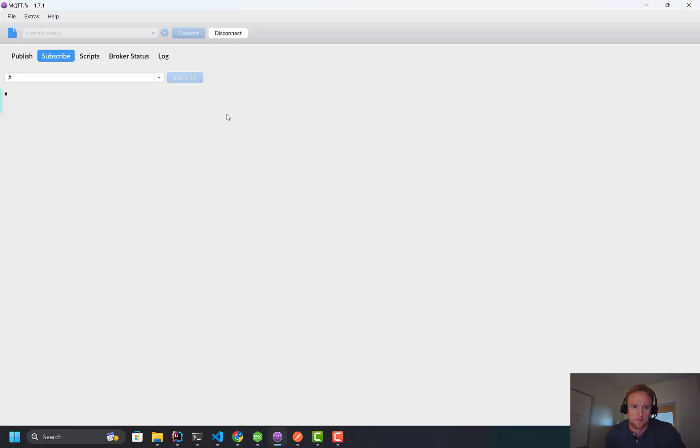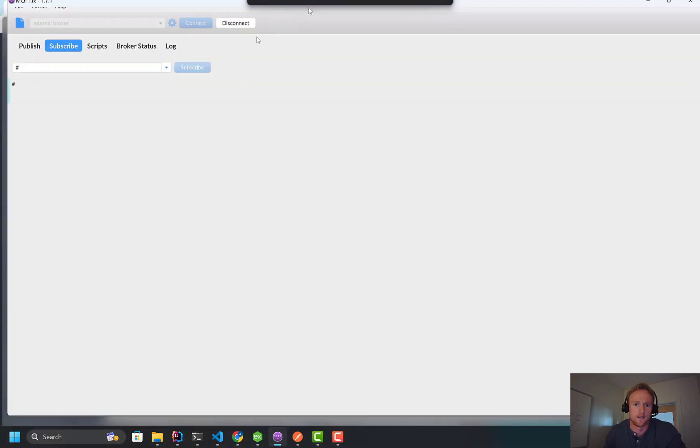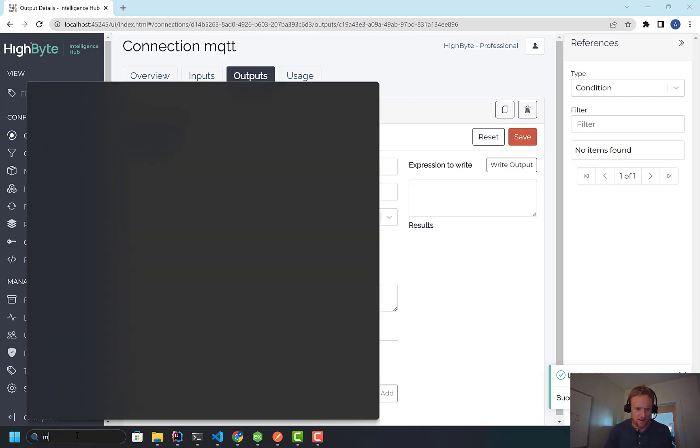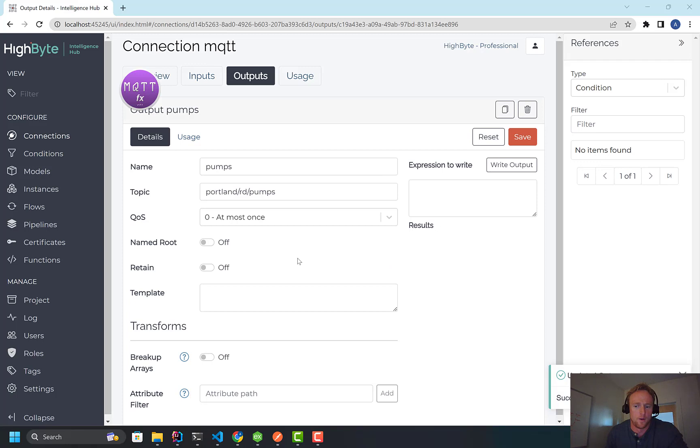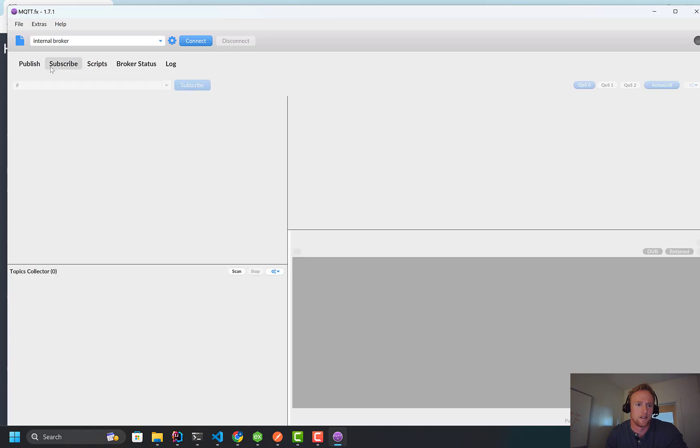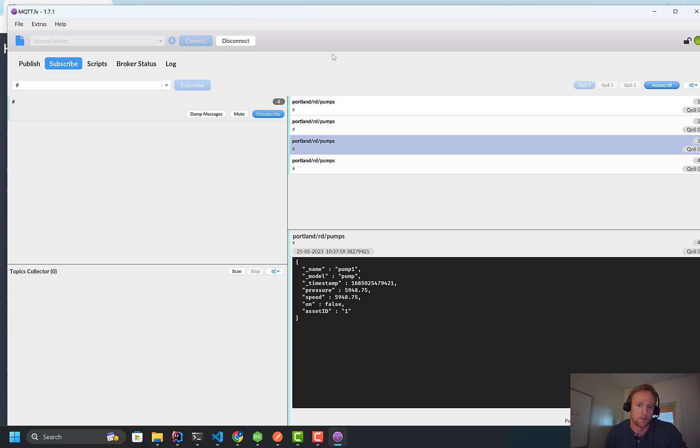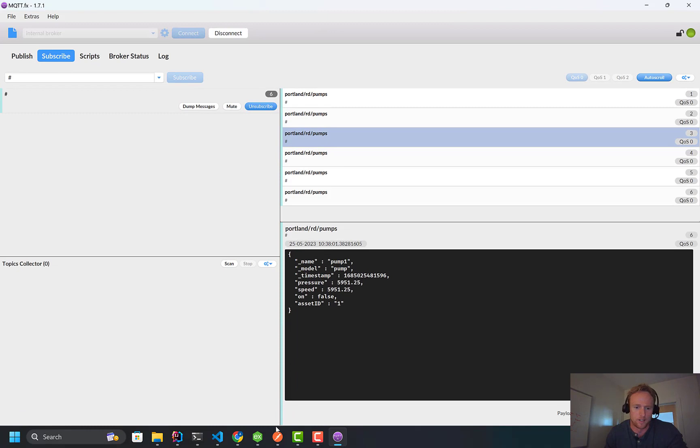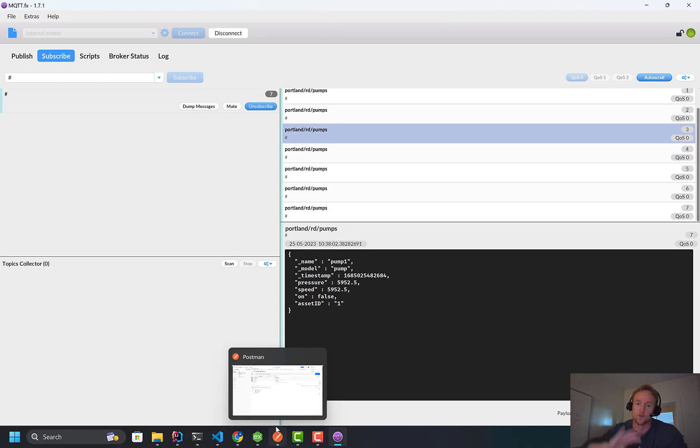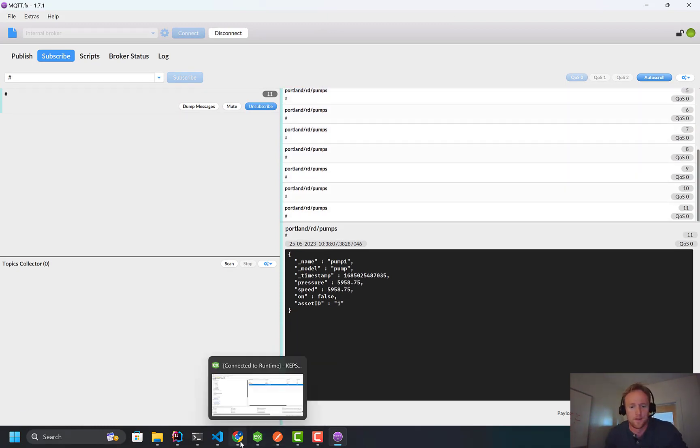And if I pull up MQTT and subscribe, my client looks like it is hosed. So let me launch that again. When I pull this up, this is the base of the UNS. So we're publishing over a Portland R&D pumps namespace. And when we connect, and I'm using the HighByte broker. But either way, you can see that data is coming through. And that flow is just publishing it once every second. And we can see some data change. So that's cool. We've done all that. That's publishing model data of the UNS. Done.